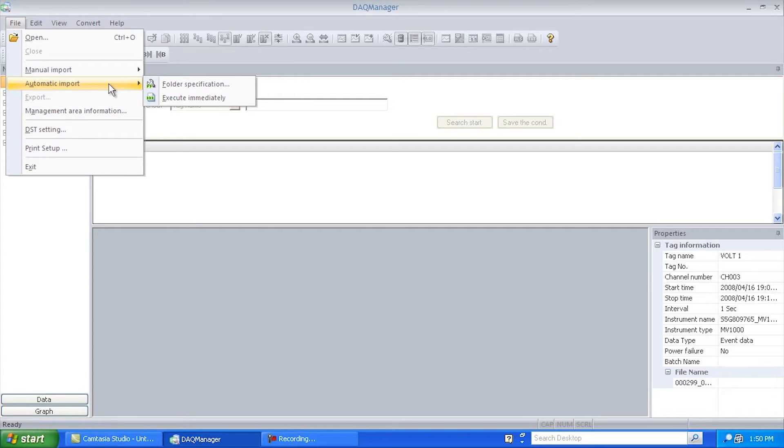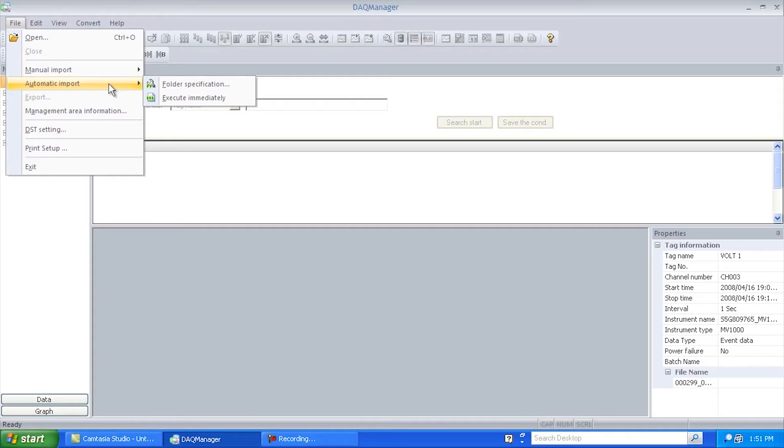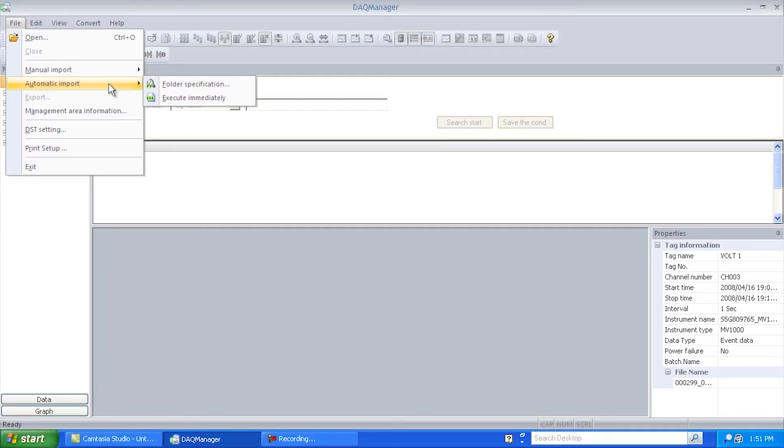Also, we have a piece of software called DAQ Explorer. DAQ Explorer is much more simpler for arranging these automatic file transfers. Essentially, you install DAQ Explorer, and then you go to each DAQ Station, give it a network address. You go back to DAQ Explorer, and within DAQ Explorer, you essentially just input your IP address or network address for each of your recorders. You hit Mount. You say, I'd like to automatically transfer files, and then you're done. The files will now just automatically, as they're created, get delivered to the folder you specified.